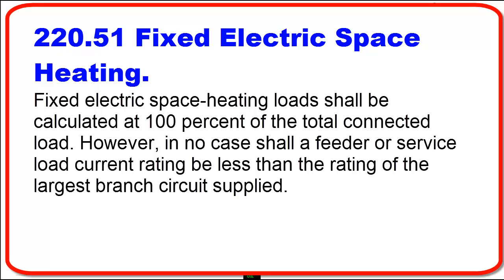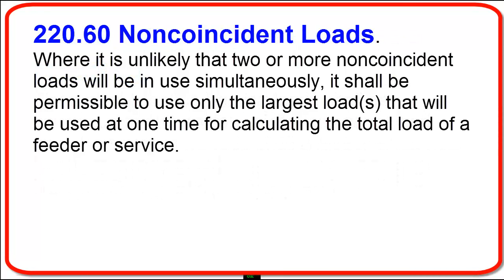So what if I have electric heat and AC together? Do I need to take both of them? The answer to that is no. And if you look at Article 220.60, non-coincident loads, it states where it is unlikely that two or more non-coincident loads will be in use simultaneously, it shall be permissible to use only the largest load that will be used at one time for calculating the total load of a feeder or service. So we are at heat versus AC. In this calculation, we are going to have a gas furnace with a 3 horsepower AC unit. So if we are doing heat versus AC here, it is going to be the AC.